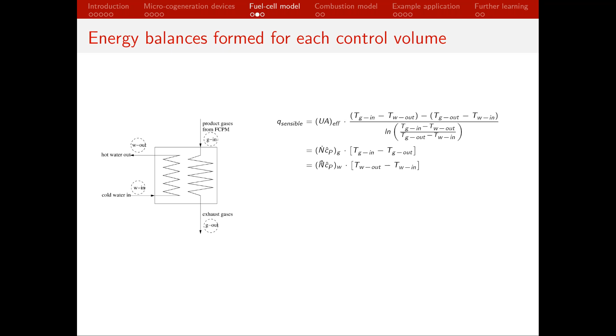So under these assumptions, we can write a set of equations now that relate the characteristics of the heat exchanger, the UA value, the flow rate of gas and water through the heat exchanger, and the temperatures entering and leaving the heat exchanger.